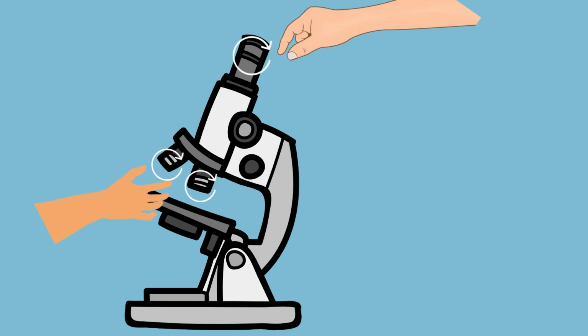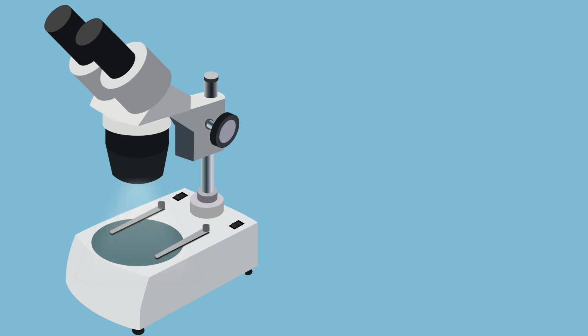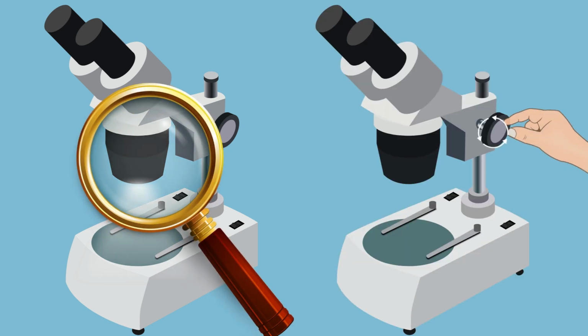If your microscope is giving you blurry images, start by cleaning the lens with lens paper. Adjust the diopter and ensure the objective lens are clicked into place. For illumination problems, check if the light source is properly connected and functioning. Adjust the condenser and diaphragm for optimal light.